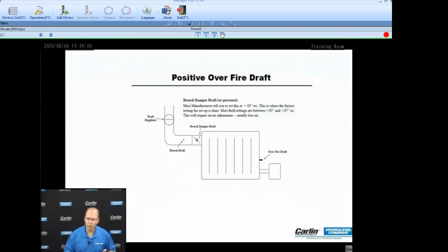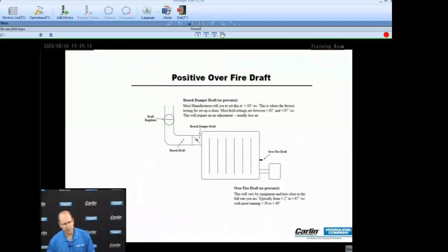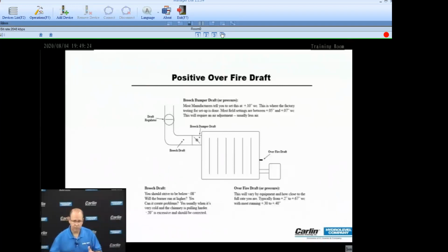Forced draft boiler is designed to hold the gases tightly in the boiler. And as those gases exit the boiler a little bit slower, that means they spend more time inside the boiler, so there's better heat transfer. It also means that they're under pressure while the combustion is taking place. Combustion, atomization, air mixture, oxygen. It gives us a better opportunity to create this mixture and better results in combustion.